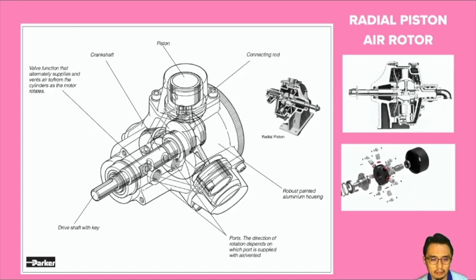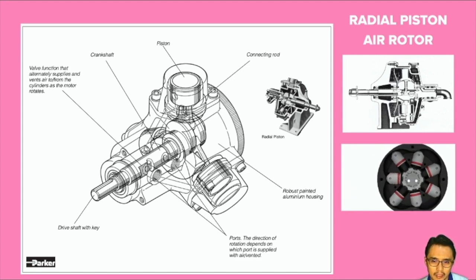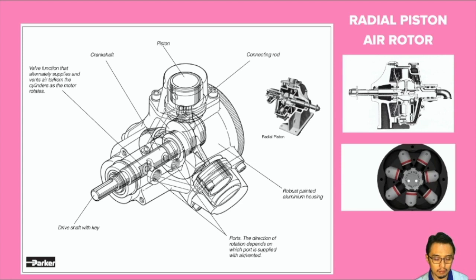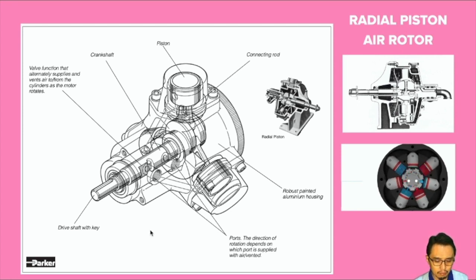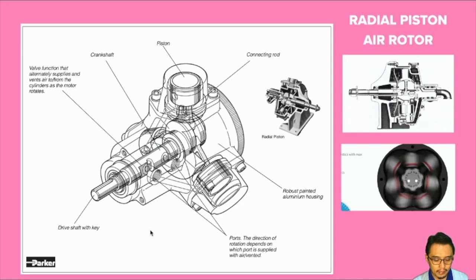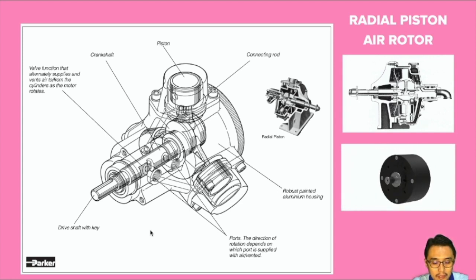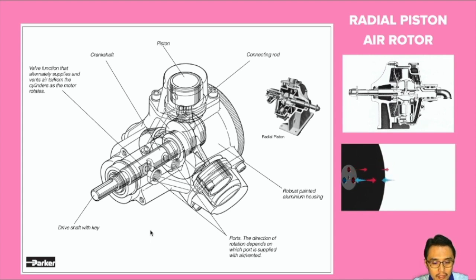The next rotational motor is the radial piston air motor. This five-cylinder piston design provides even torque at all speeds due to the overlap of five power impulses occurring during each revolution. At least two pistons are on the power stroke at all times. The smooth overlapping power flow and accurate balancing make this motor vibration-free at all speeds, which is especially noticeable at low speeds when flywheel action is negligible. This air motor has relatively little exhaust noise, which can be further reduced by use of an exhaust muffler. It is suitable for continuous operation using 100 psi air pressure and can deliver up to 15 horsepower.